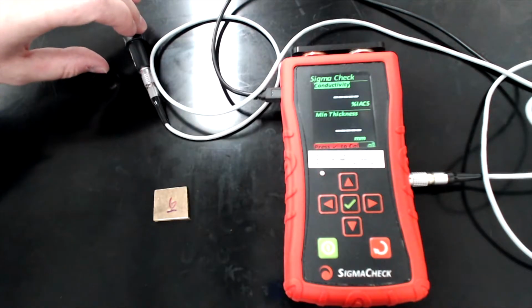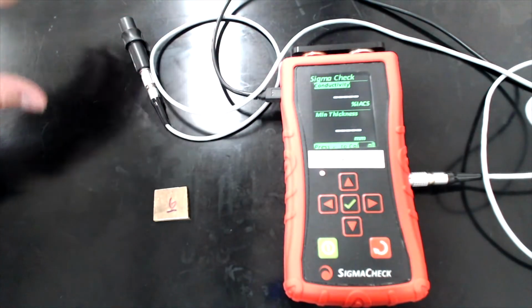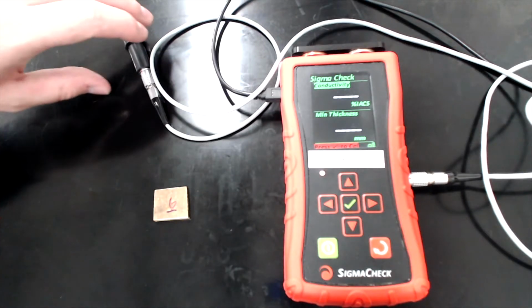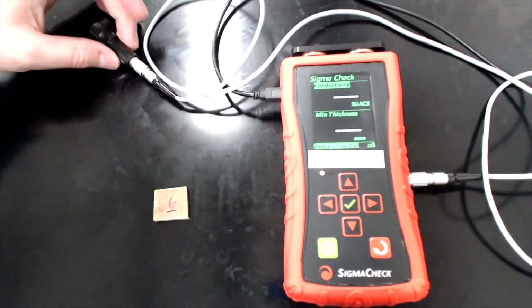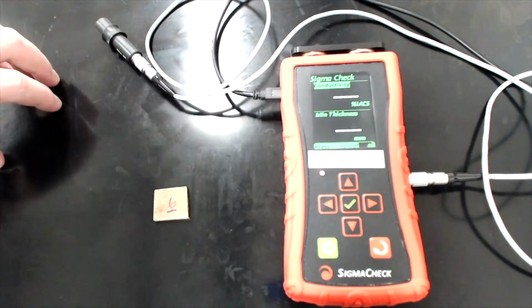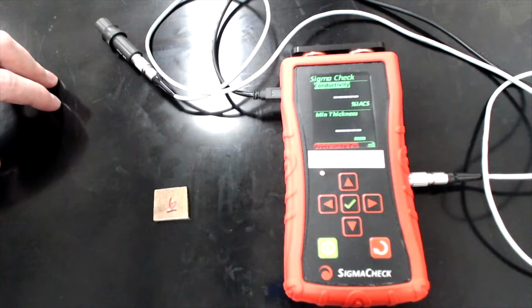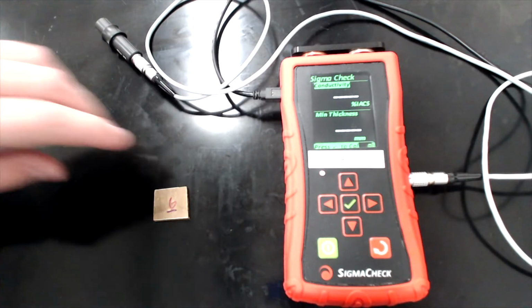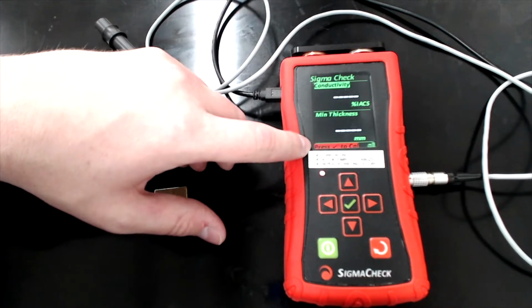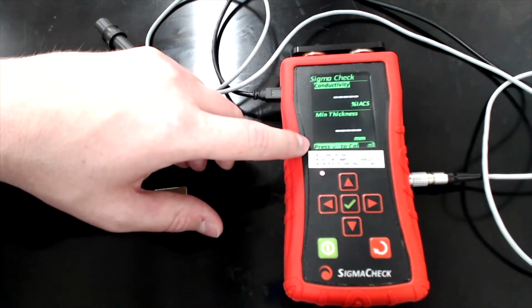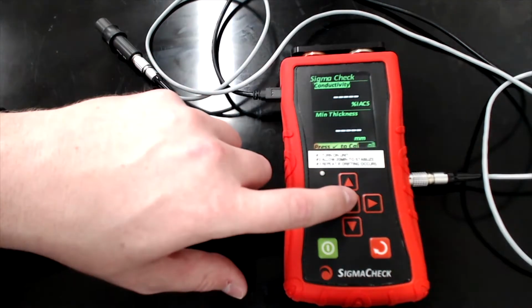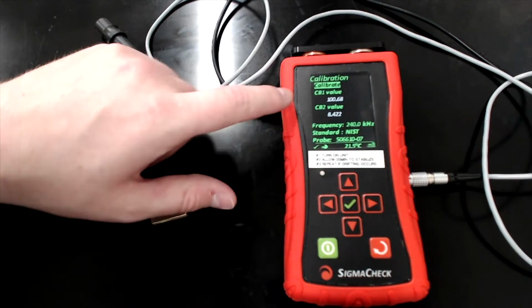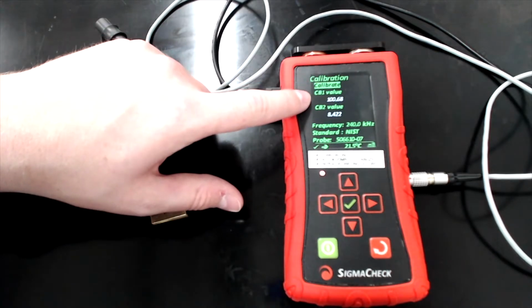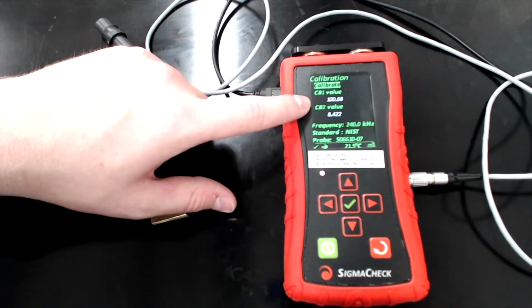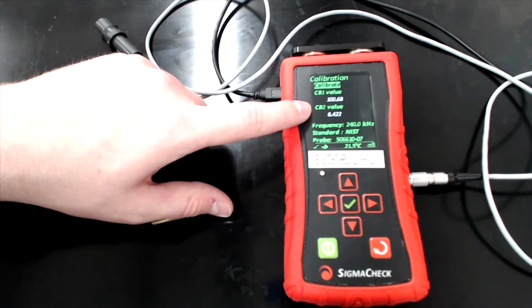To review, we've turned it on. We've got the power in so that if the battery is low, it won't shut off. We've plugged in the probe over here to the side, and we let it stabilize for 20 minutes. So the first thing you might notice is this thing blinking down here, and it says press the check mark to cal, so calibrate. So I'm going to hit the check mark, and up here you see calibrate, and then it gives you the two values.